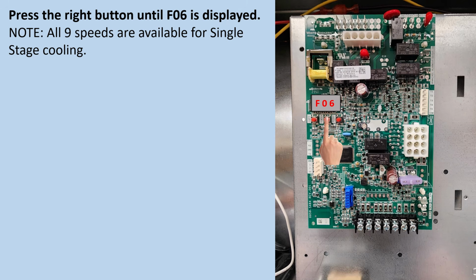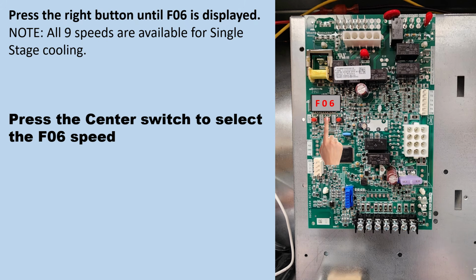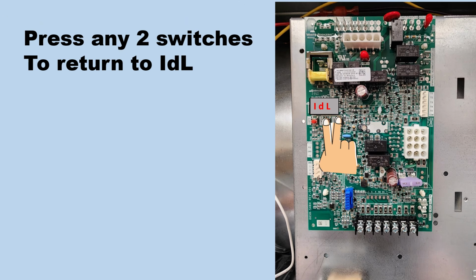Press the right button until F06 is displayed. Note, all 9 speeds are available for single stage cooling. Press the center switch to select the F06 speed. Press any two switches to return to idle.